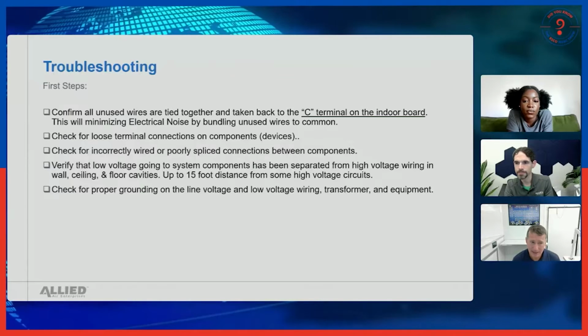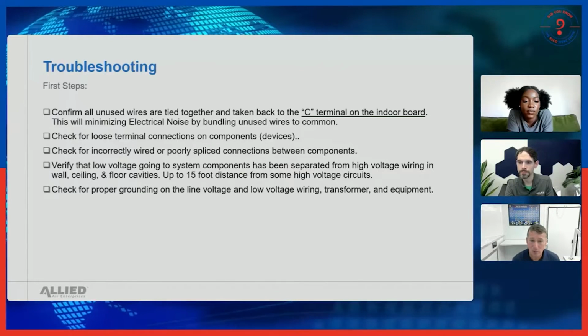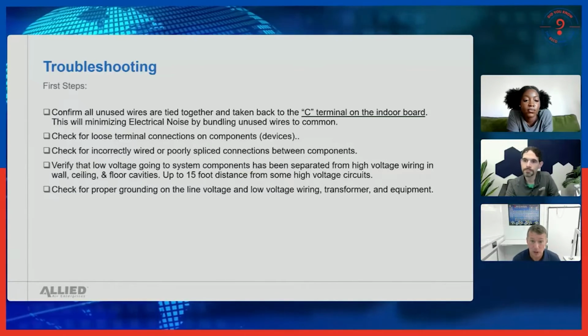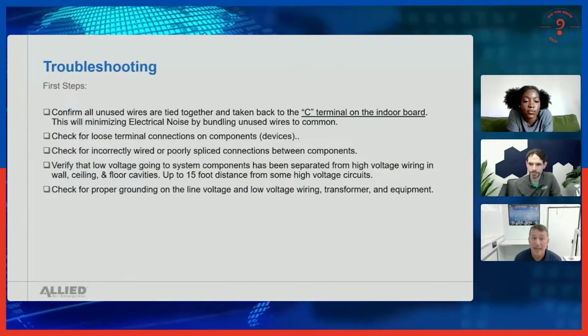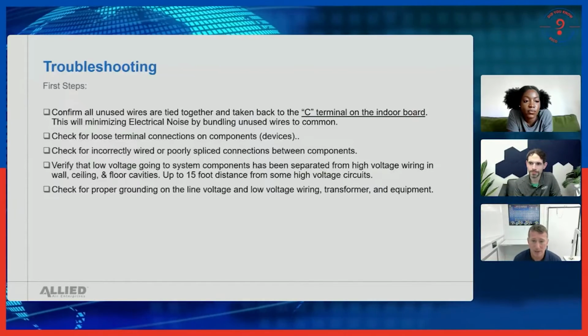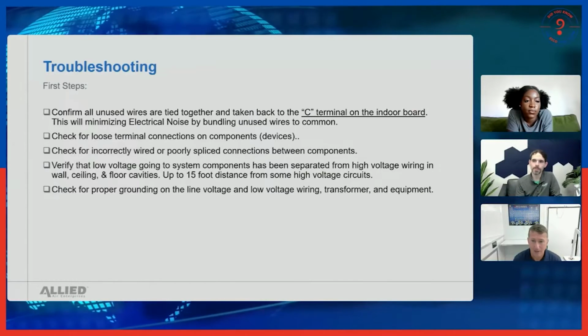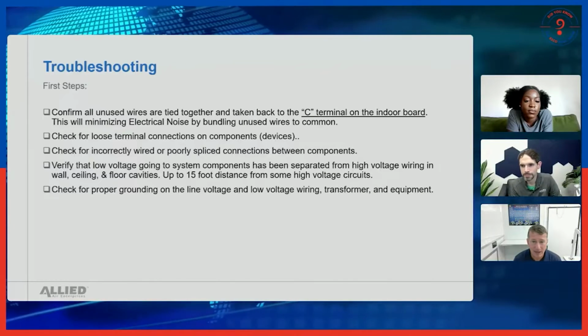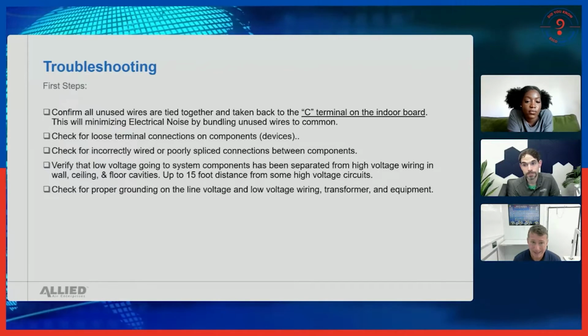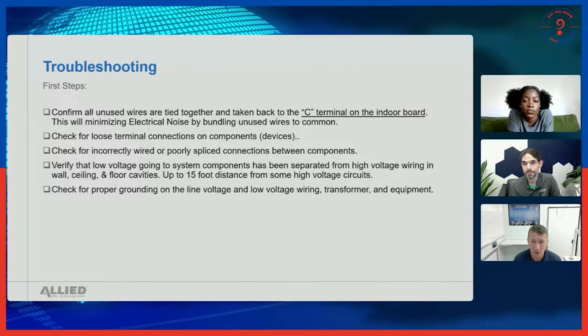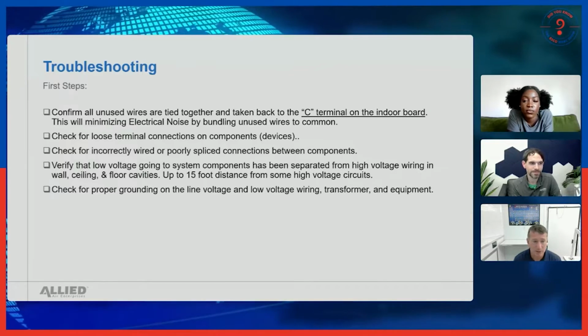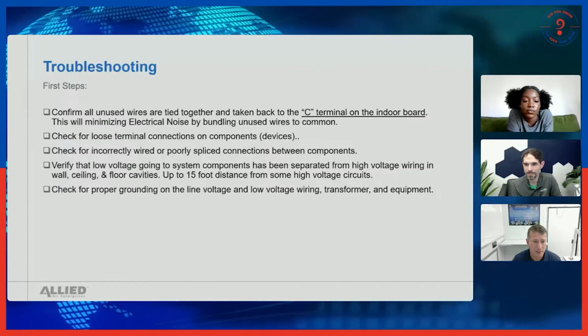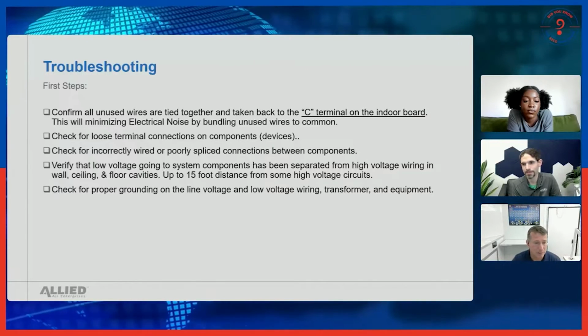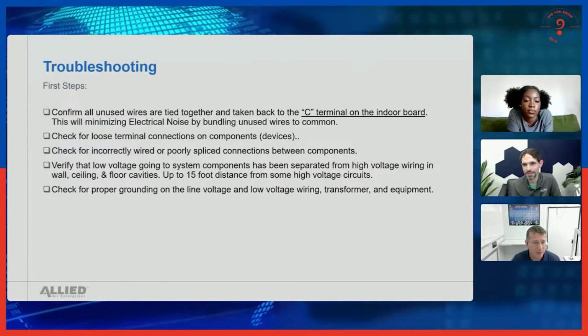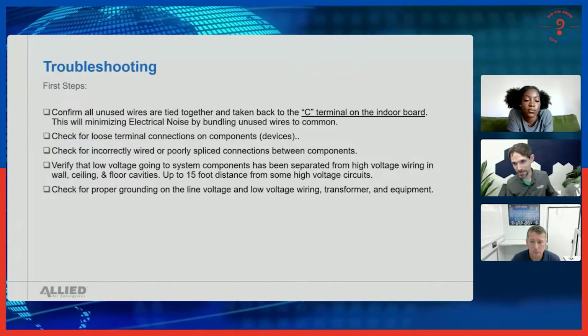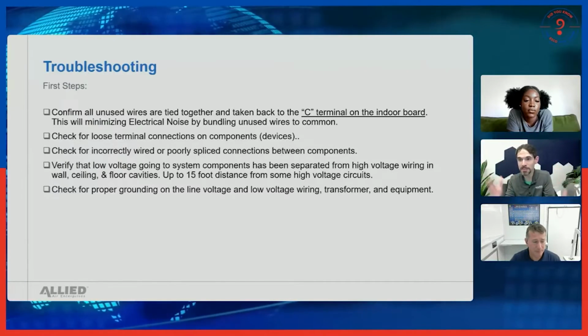Remember, that existing thermostat wire could have had corrosion inside that wire nut, and because it was a load with current passing through it, it might have still worked. But when we talk about something communicating, with very low voltage and very low amperage, now we actually have resistance on that communicating line because of the corrosion. So the first thing to do is cut any wire nuts out, make sure they're clean, with fresh new insulation. Running new wire is not a bad thing, especially with communicating systems.